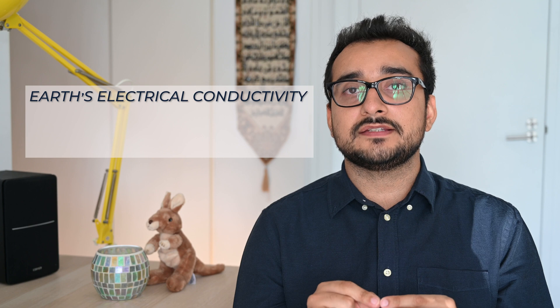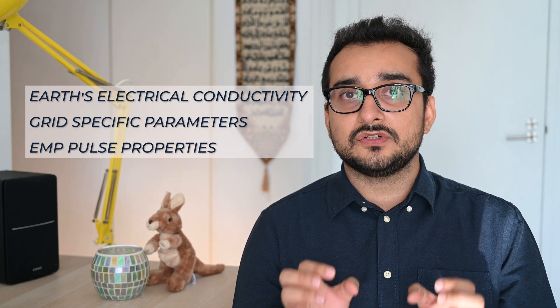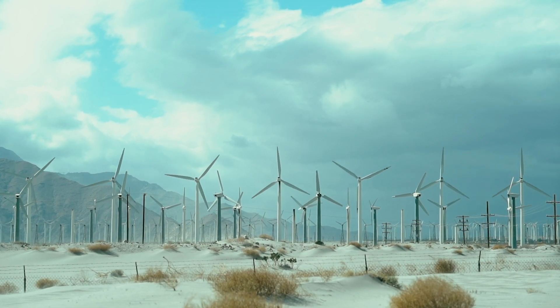Its effect on the electric grid is strongly determined by the Earth's electrical conductivity near the area of impact, the grid-specific parameters, and the magnetic properties of the EMP pulse. To understand how this could affect the grid, one key measurement is to map out the surface impedance of the Earth everywhere that the grid goes, including measuring local variations in the magnetic field and using voltmeters to measure time-varying electric fields at those locations.